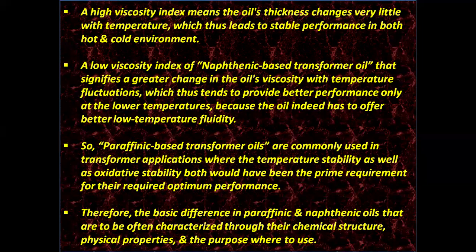A low viscosity index naphthenic based transformer oil signifies a greater change in the oil's viscosity with temperature fluctuations, which tends to provide better performance only at lower temperatures because the oil has to offer better low temperature fluidity. So, paraffinic based transformer oils are commonly used in transformer applications where temperature stability as well as oxidative stability would be the prime requirement for optimum performance.